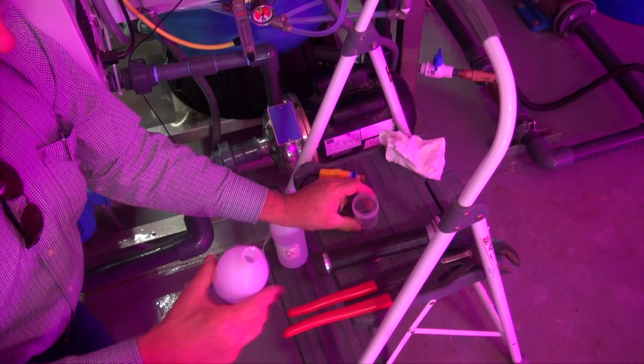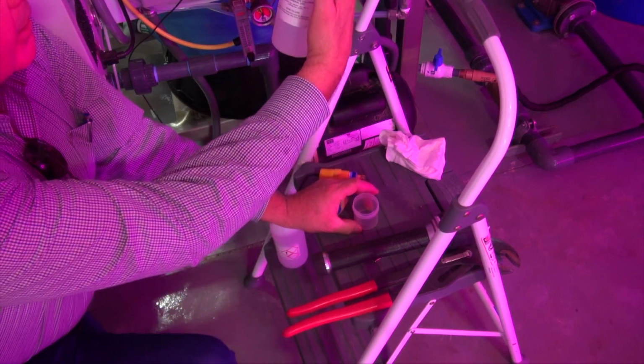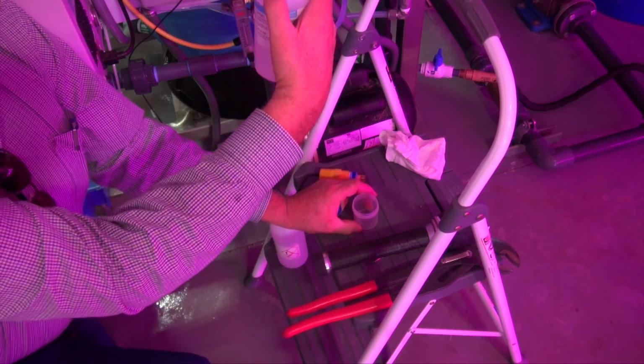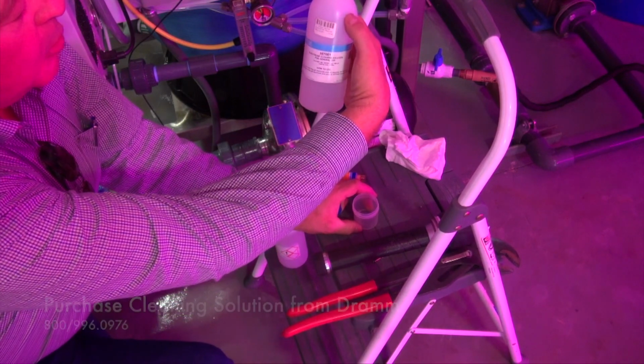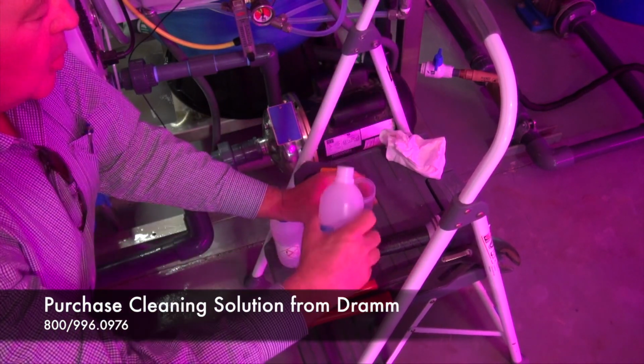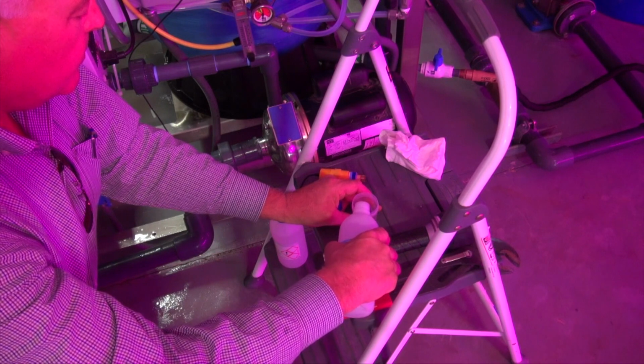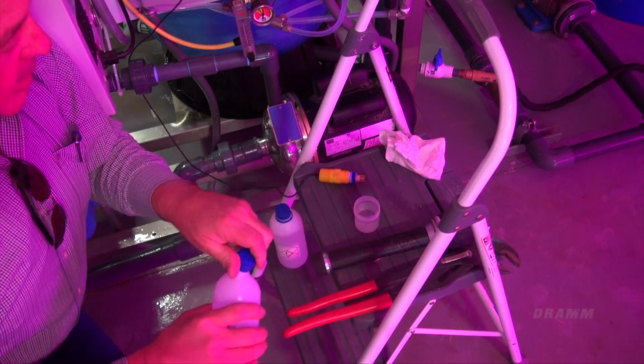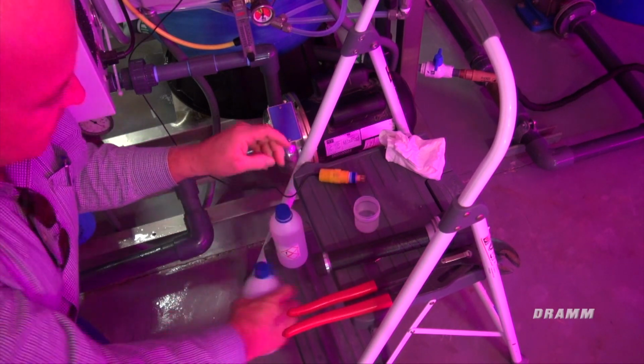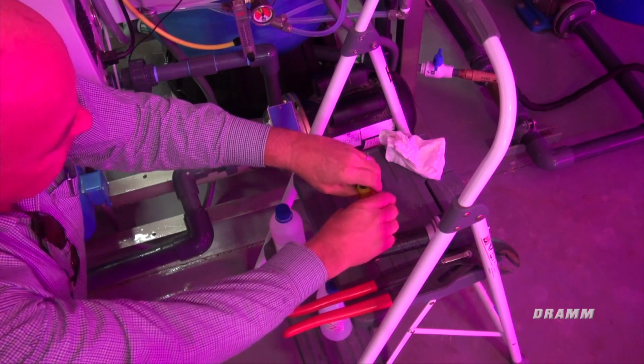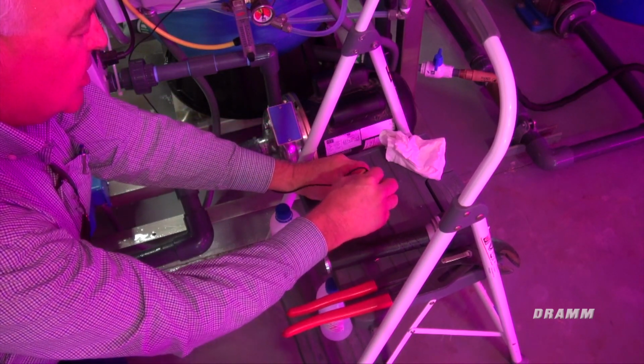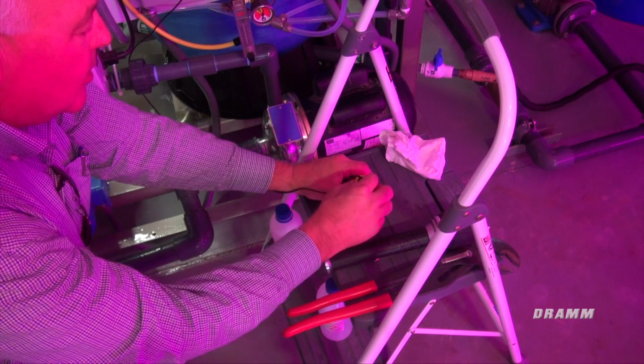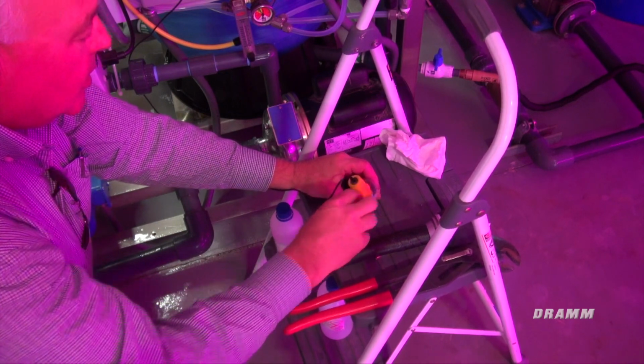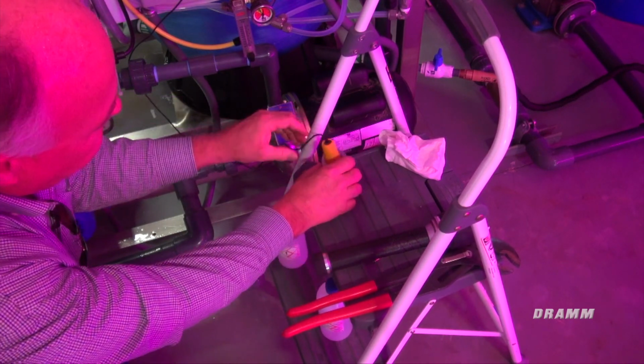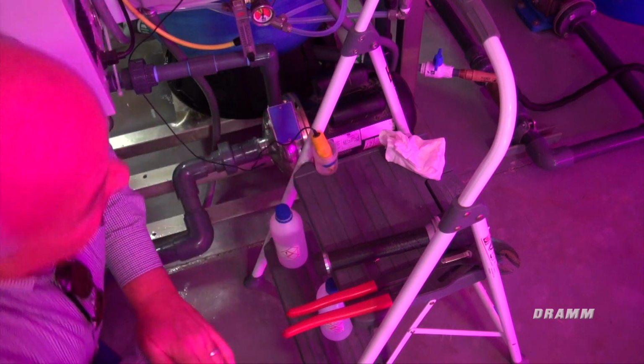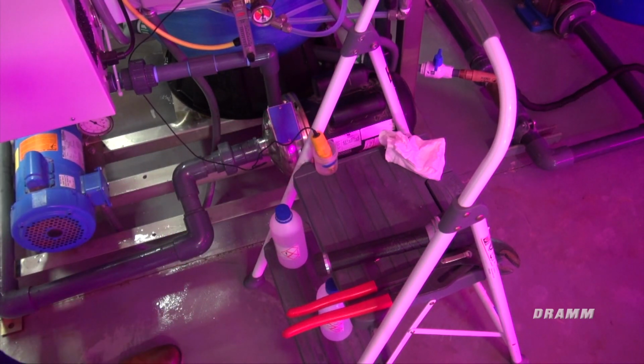Before I reinstall that, we're going to use an electrode cleaning solution to dip that probe in and clean it up a little bit more before we reinstall it. And let it sit in there for a few minutes before we put it back in. So I'm just going to swish it around in there a little bit, and then we're going to just let it sit in that solution for a few minutes and then put it back in to the system.